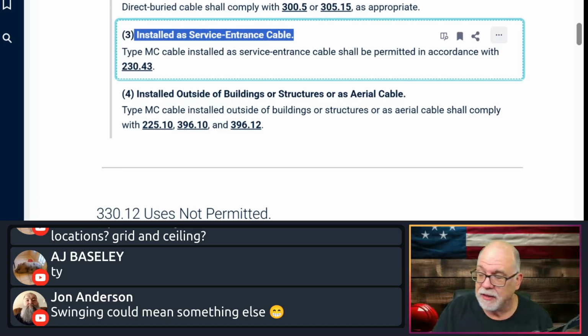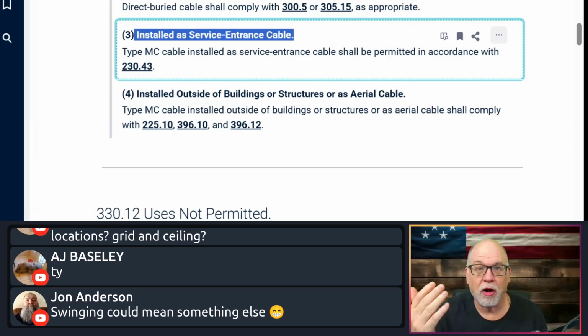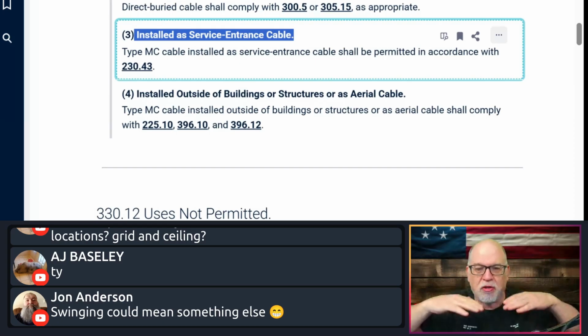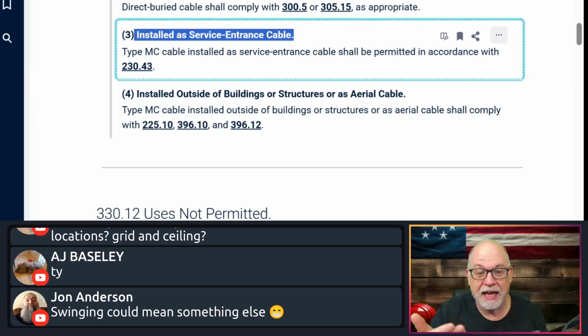Just remember, and I run into this with people, they do want to use MC many times. Again, it's a lot more work. I just use SE cable unless you're in an area that doesn't allow it. And by the way, SE cable is still not for use where subject to physical damage, no different than MC. Even though it looks harder, it's got an armor, it's got to meet a crush and impact test. At the end of the day, MC cable is still not for installations where it's subject to physical damage, believe it or not.